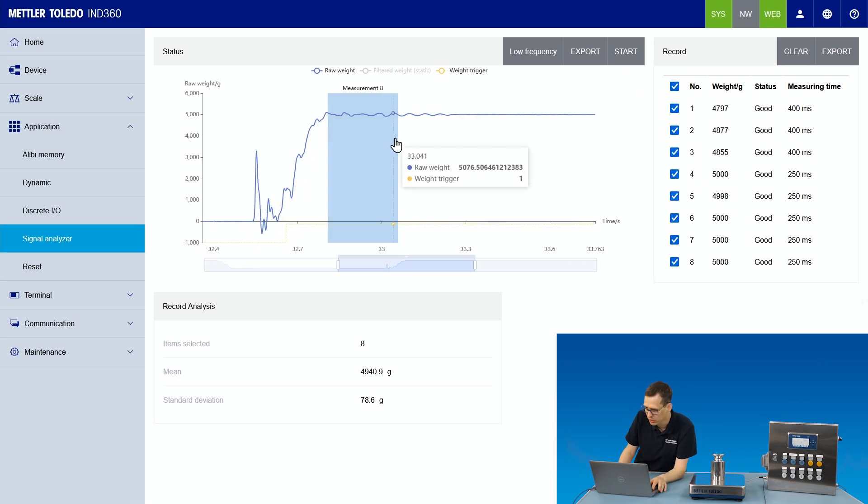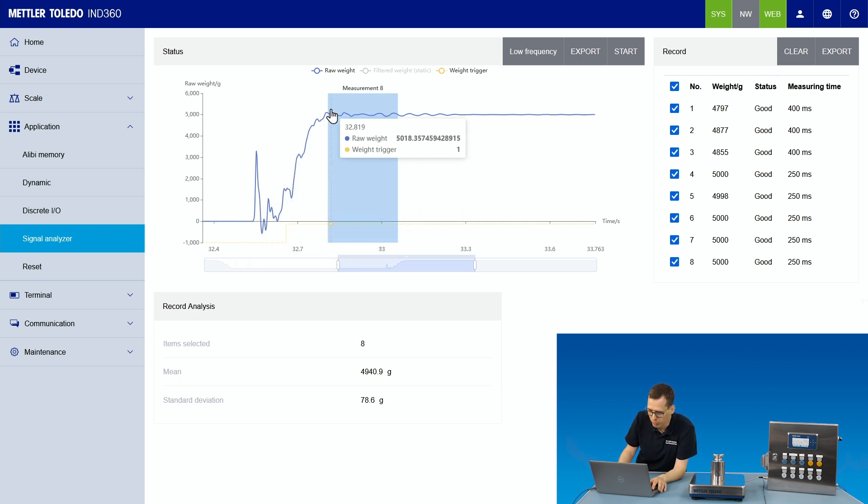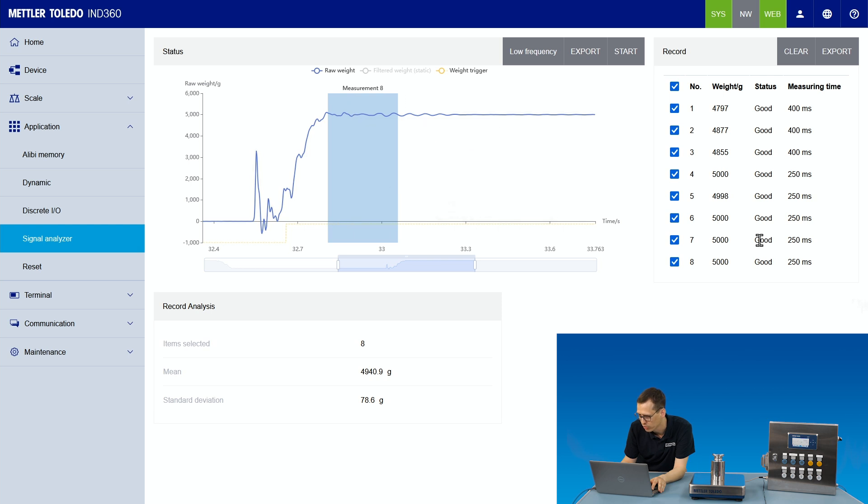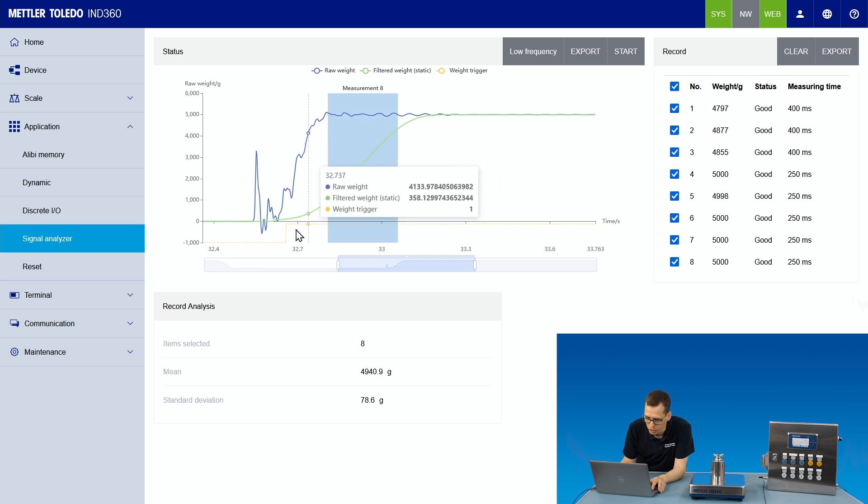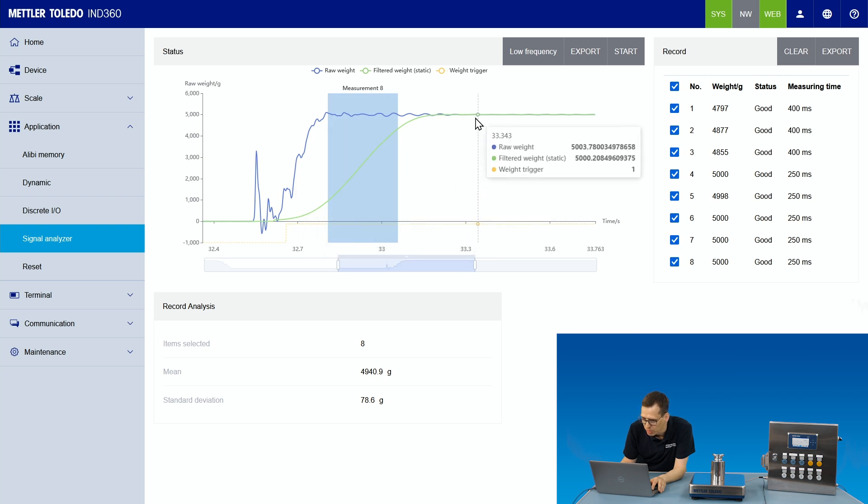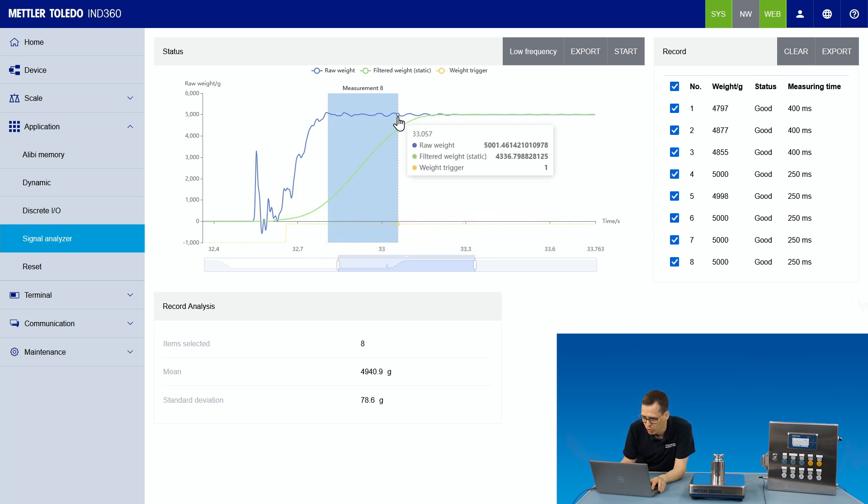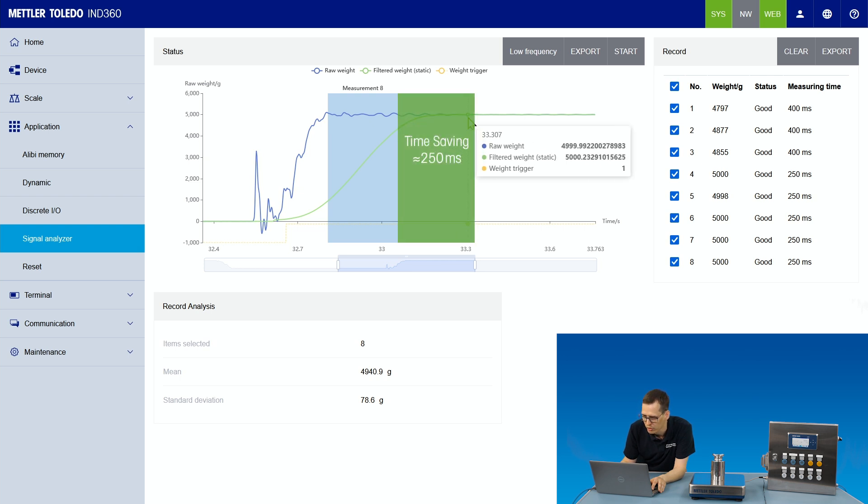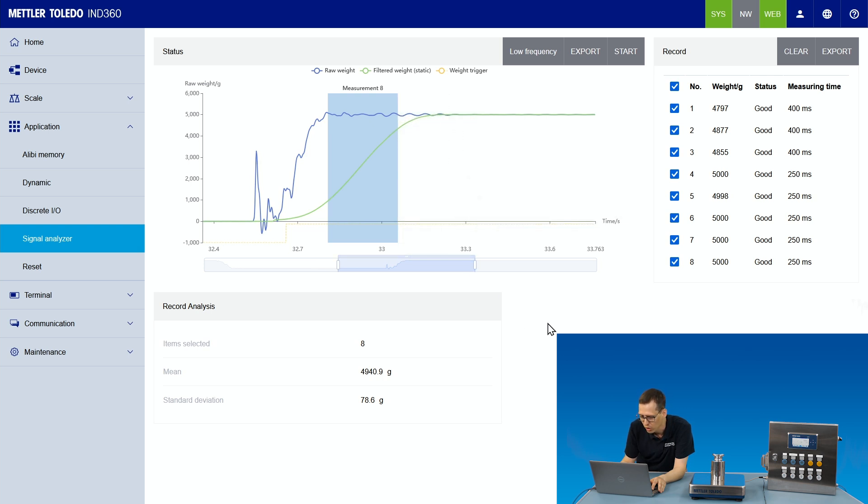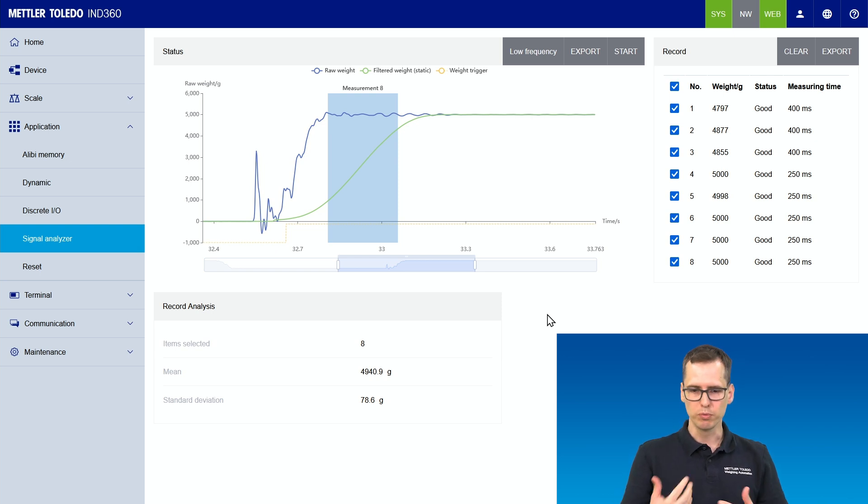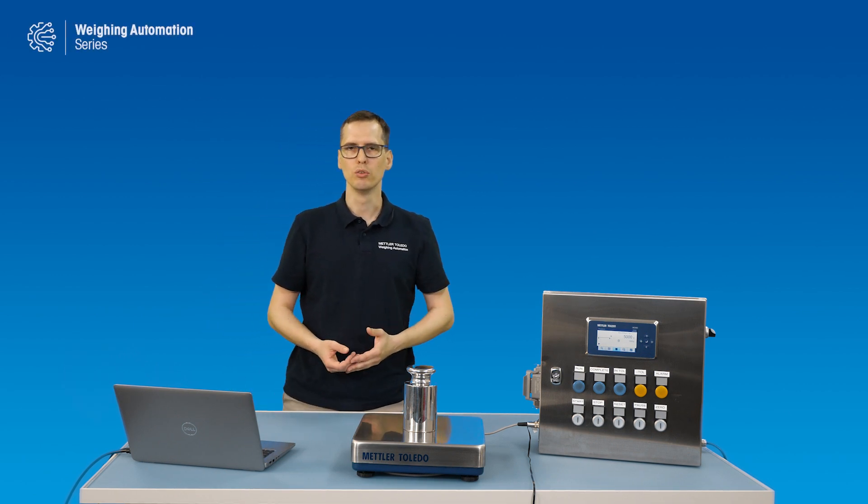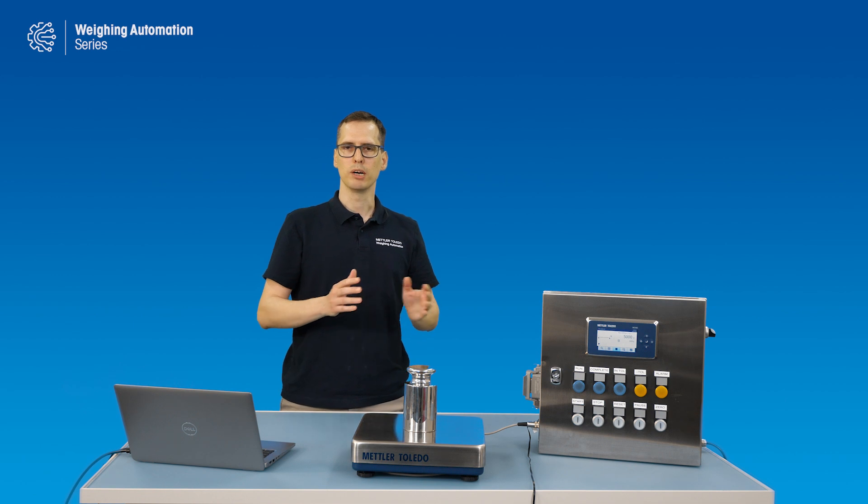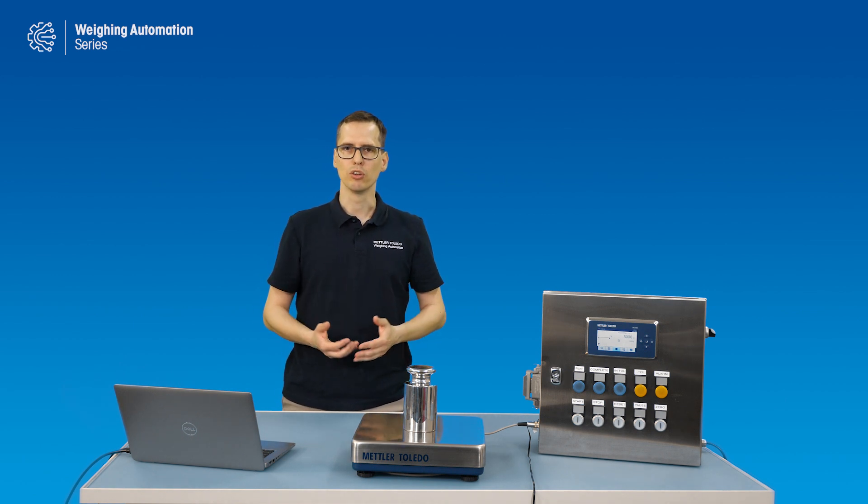If we can look into the signal. So we see it, the weight being applied and when the weight is starting to be fully on and but it's still not stable but it's now fully on. We start capturing the weight and this gives us now very consistent results. I can also show you the filtered weight signal which is now the green line. The green line actually triggered the weighment but the green line stabilizes somewhere around here. And we already got the final weighing result here. So looking again at the time index, we save here about 250 milliseconds until we got a stable weight reading. So we save 250 milliseconds here with every weight reading by me applying the weight manually just with one round of tuning. We could of course now try to fine tune the system even more by adapting the measuring time, by adapting the trigger point and so on.